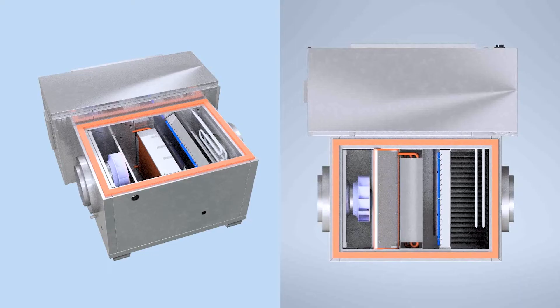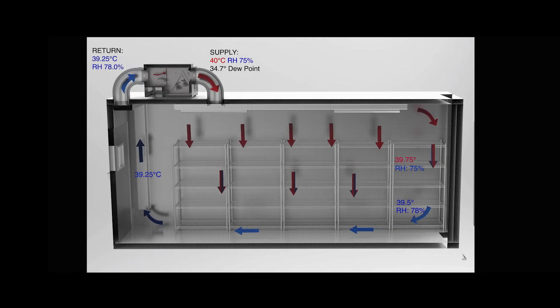dry bulb temperature, the air is returned to the conditioned space. Utilizing this method, very precise humidity control is achieved. The system does not distinguish between humidifying and dehumidifying; it is always setting a dew point and reheating.